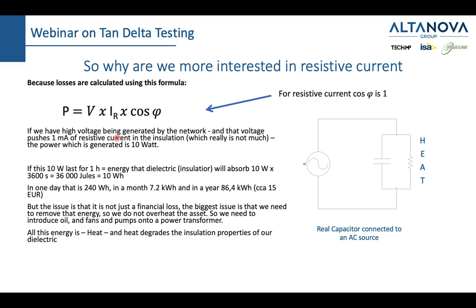Now let us take one example. Let's say that we have a 10 kilovolt transformer, and if we have a 10 kilovolt transformer, let's say on the primary side, and only 1 milliamp of resistive current, so it's 1/1000th of an amp, the power which is dissipated is 10 watt. 10 watt per se is not a big power.